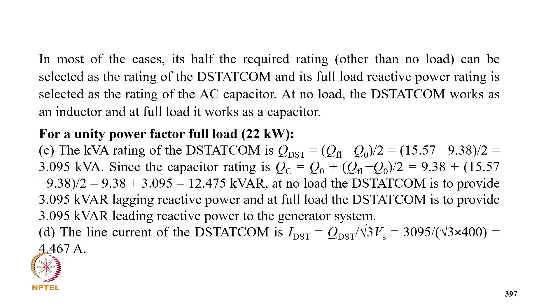4.467 ampere. For 0.8 lagging power factor load, the kVAr rating of the system QST equal to QFL plus Q load minus Q0 by 2, so that comes to 11.345 kVAr. Since the capacitor rating is QC equal to Q0, that is typically 20.7 kVAr. At no load the STATCOM supplies the load lagging reactive power.